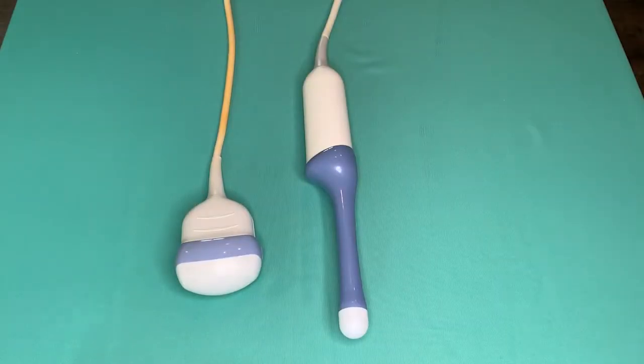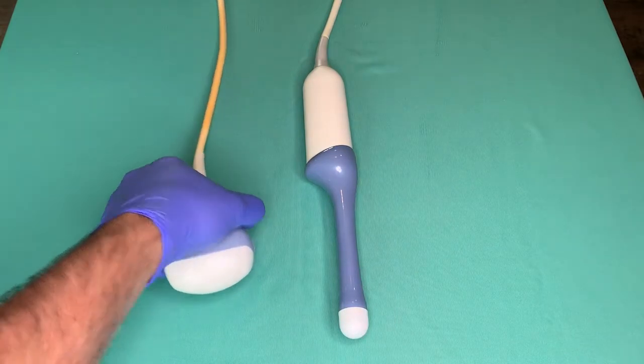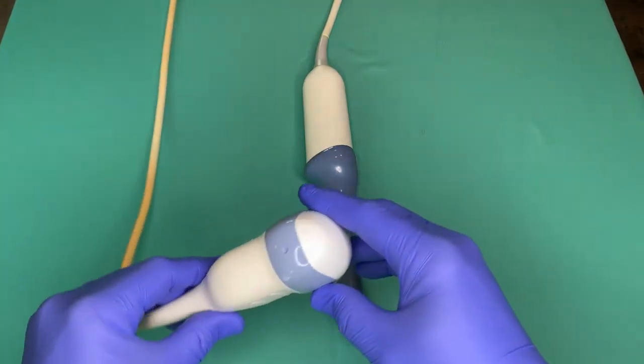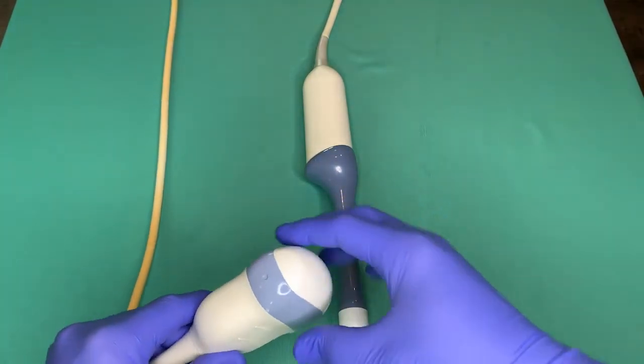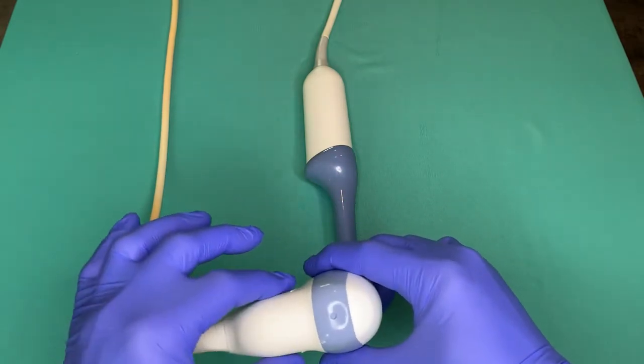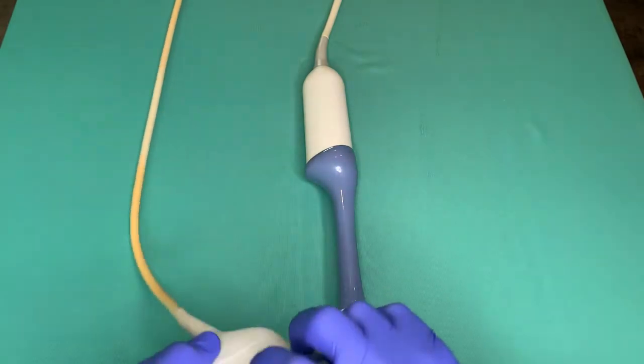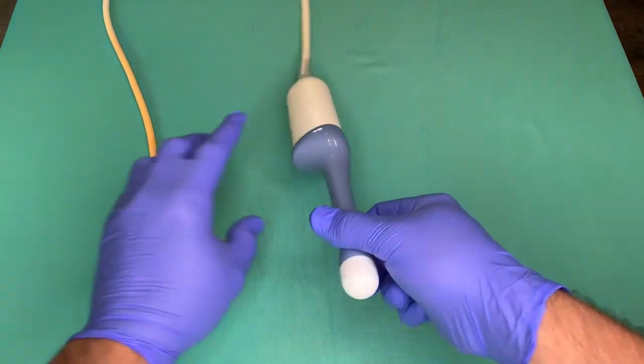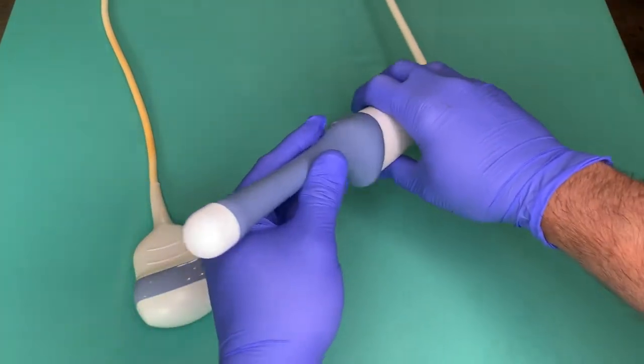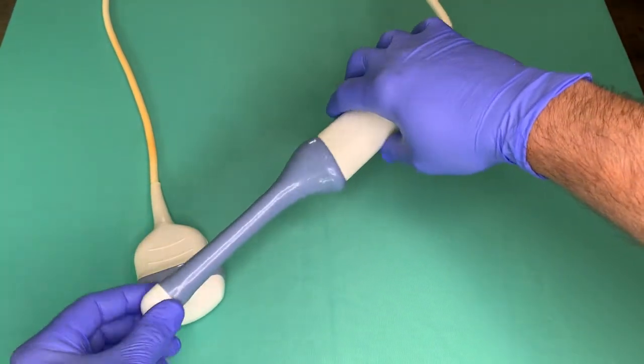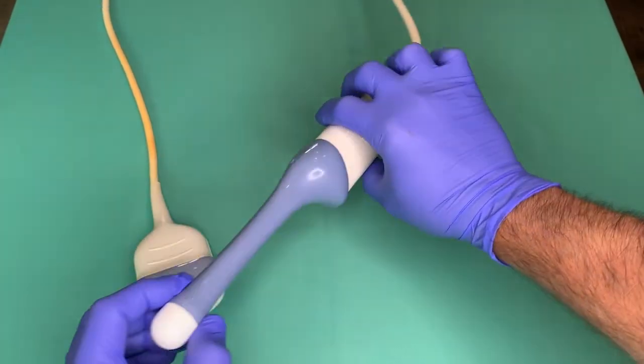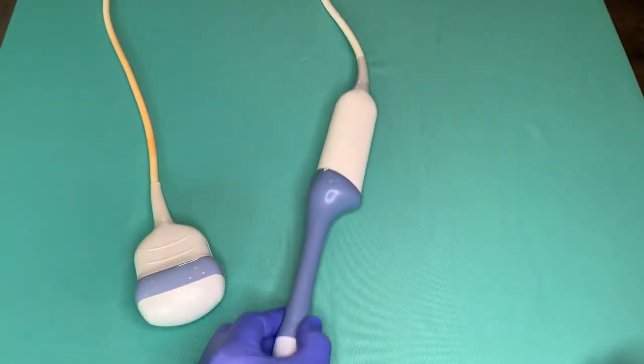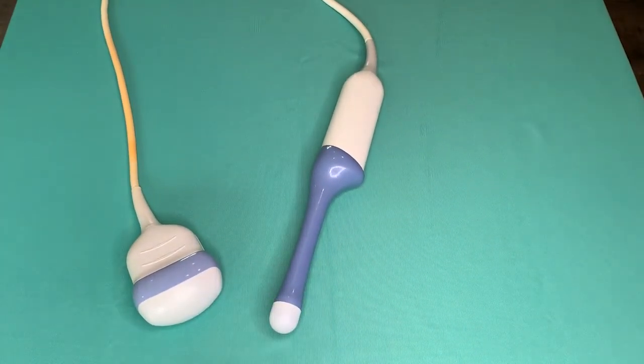The scan head of a 3D probe contains not only sensitive electronics, but also complex mechanics, and it's oil-filled. The scan head is typically a 3-piece design consisting of a dome, upper probe housing, and lower probe housing. Traumatic impacts can damage and dislodge mechanical components underneath the dome, as well as break the oil-filled bladder, causing a leak.